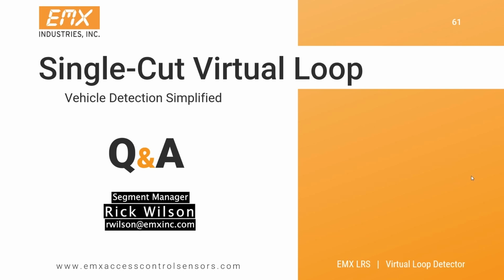Another question we have here is how do these sensors perform in detecting motorcycles? As long as they have ferrous metal, that would not be an issue. I would recommend drive testing those for your initial install to make sure we're calibrating them, because we can adjust the sensitivity down and up as high as a 9 or an 8 in that detection. Those should detect motorcycles no problem.